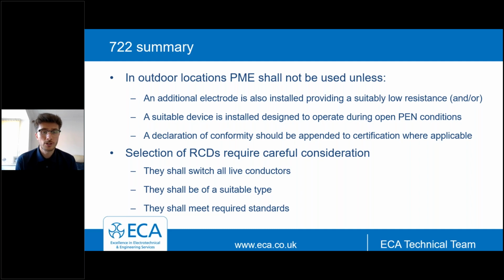So in outdoor locations, PME shall not be used unless one of the requirements within Regulation 722.411.4.1 are fulfilled. Some of the key bits there: the possibility of an additional electrode being installed, connected to the PME system, and that providing a suitably low resistance. Other options were a suitable device installed to operate at certain conditions or operate during open PEN conditions.